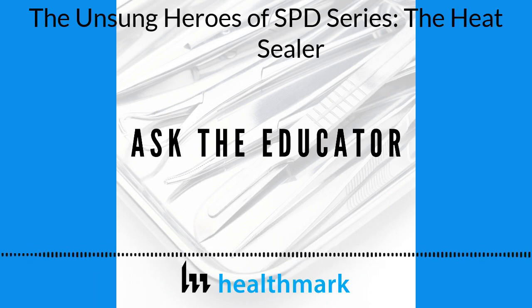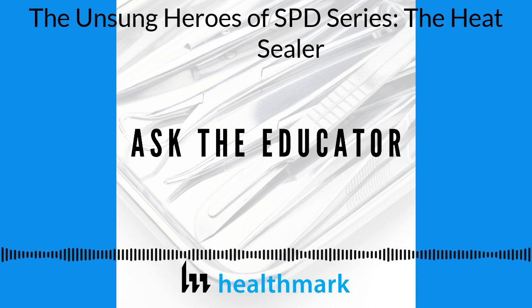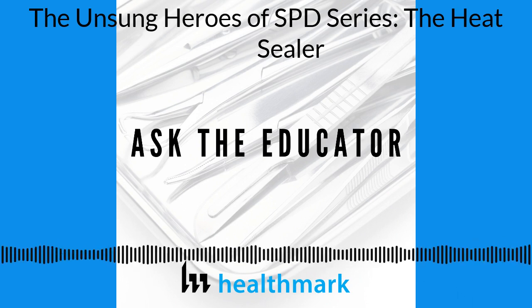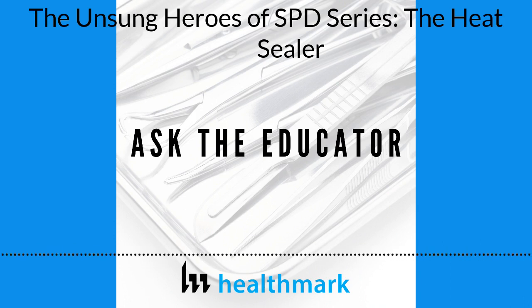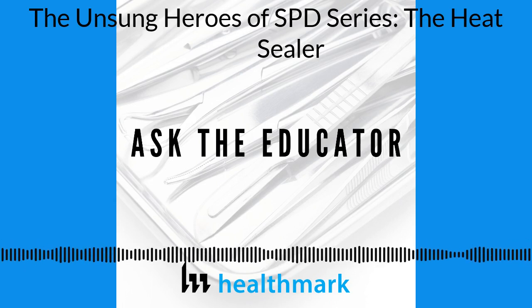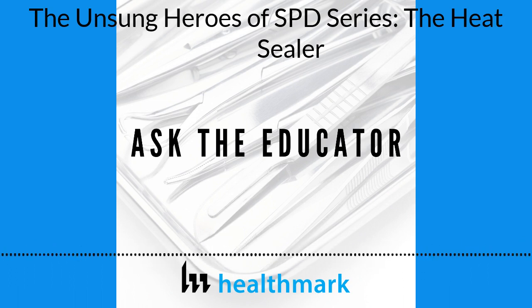It's really quite simple, but the problem is if you don't change the temperature, depending on which pack you're using, whether it's Tyvek or the steam one, paper plastic one, you could end up with seal problems, or the machine's not performing to its standard, and the seal's not as strong. So there's definitely maintenance and quality checks involved that need to be done. Obviously, even training too. I've definitely had my share of experience with poor seals on peel pouches, unfortunately. Let's try to give people some direction on how to decrease that from happening.